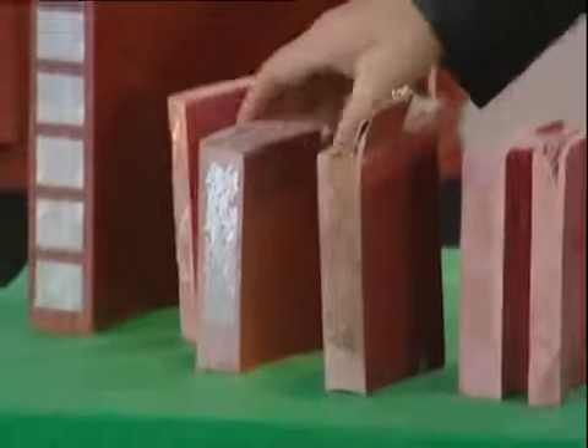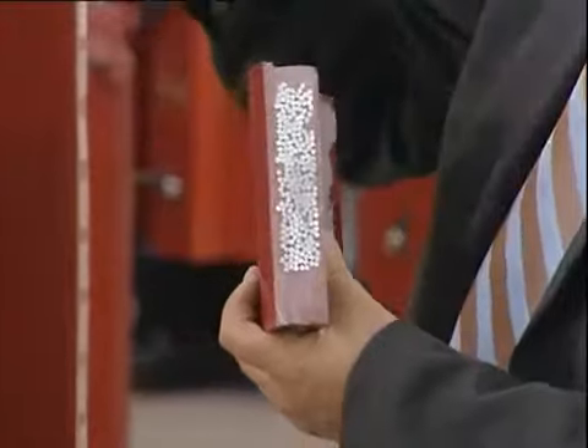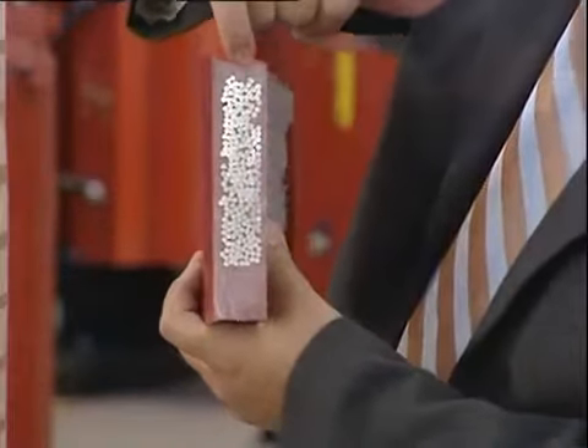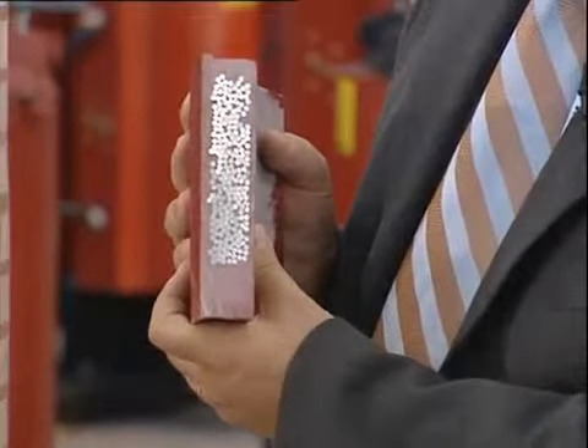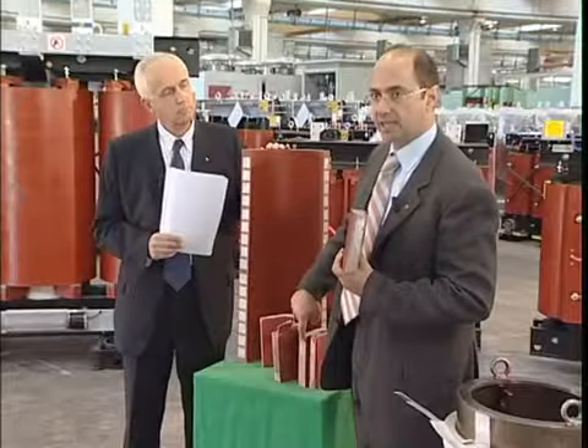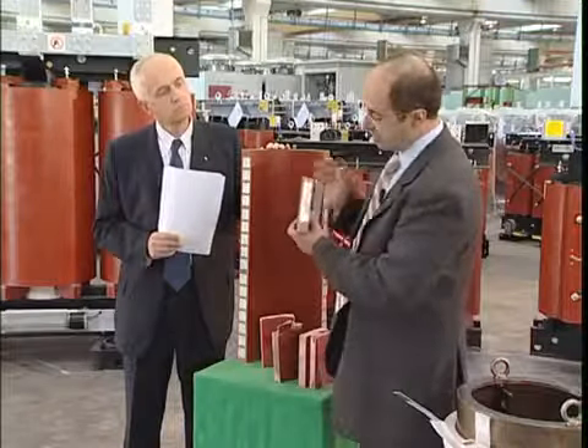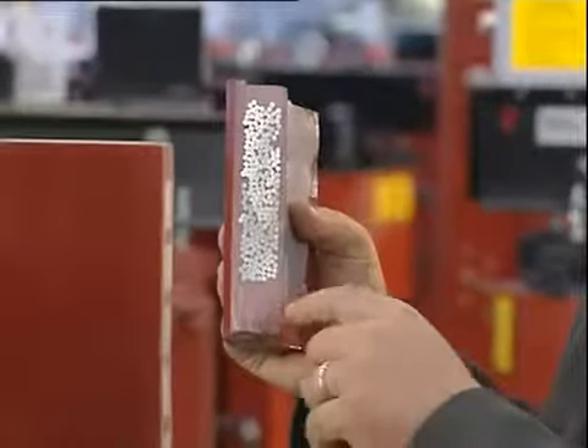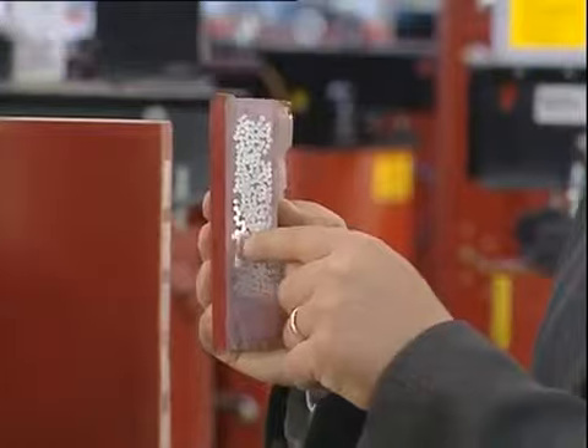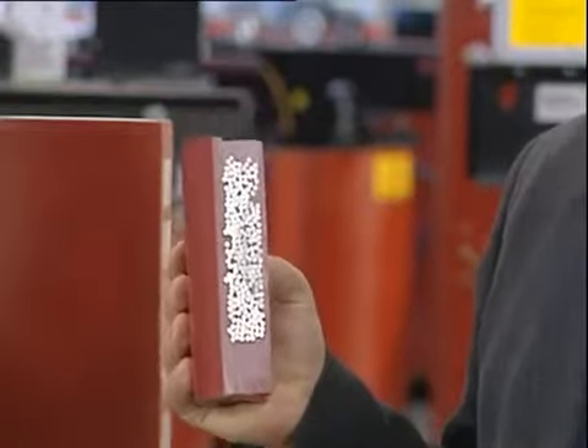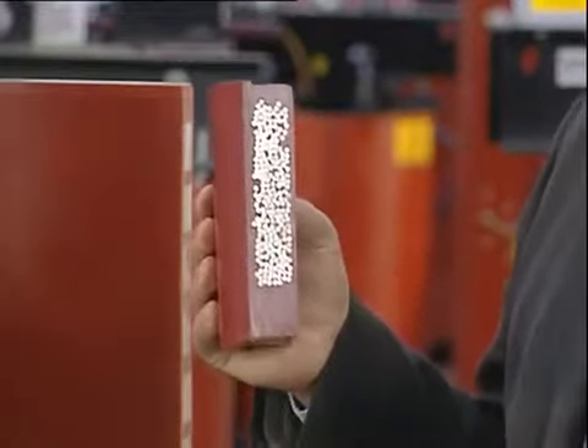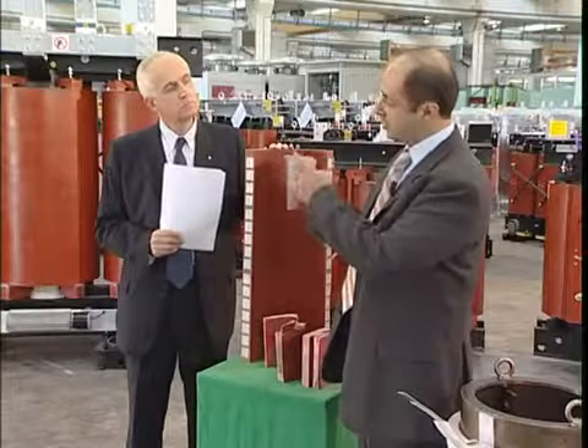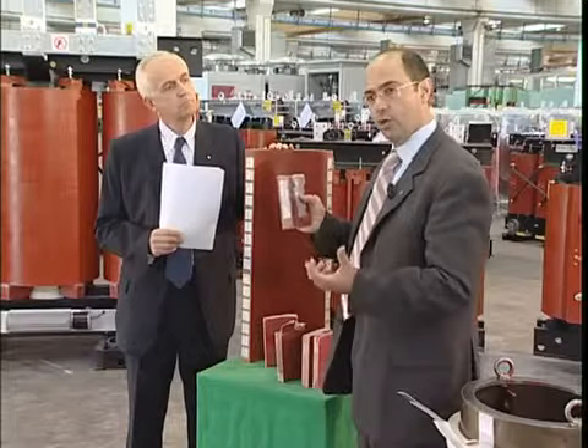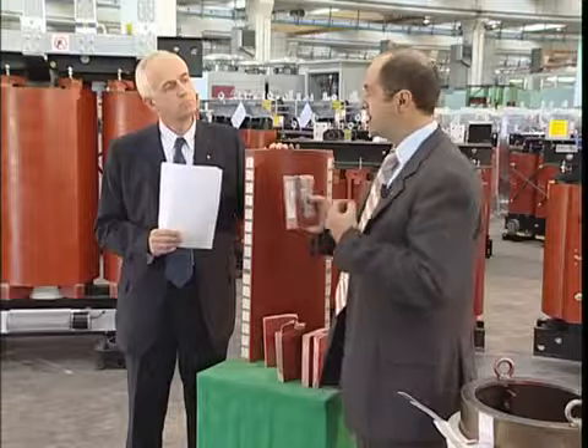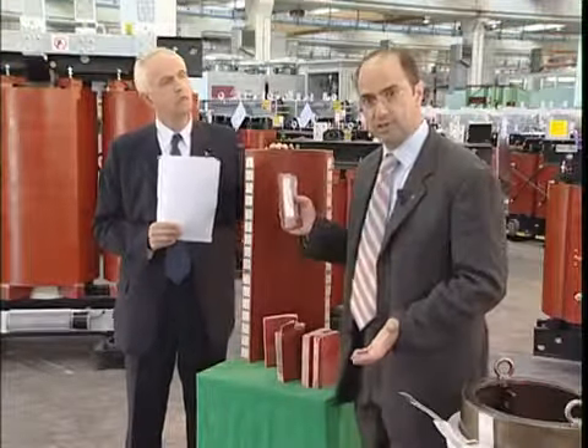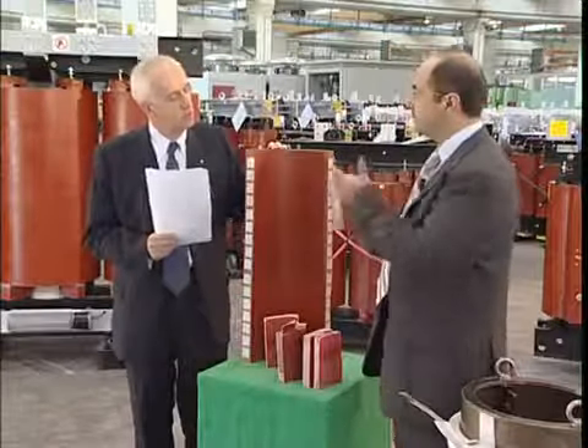Any other examples? Another example is the casual winding dropped wire technology. Here we have enamel-insulated circular aluminium conductors, while in the previous case we had tape-insulated rectangular strip conductors. In this winding, the turns are arranged starting from this position and then go up following more or less this pattern. However, since this arrangement is casual, there will not necessarily be a potential difference between two conductors. Almost certainly there will be adjacent conductors with a potential difference equal to several times the turn voltage. Two conductors can even be adjacent with a voltage which is some dozen times the turn voltage.